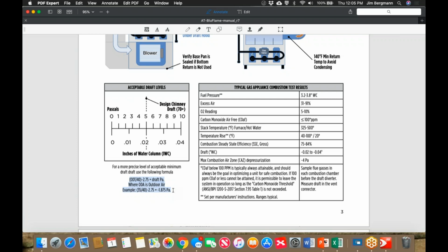It doesn't affect the appliance unless it's connected physically, like an oil burner is connected to the draft. So the draft plays a huge role in the amount of secondary air that is introduced through the combustion chamber. When you have a draft hood and it's connected to the appliance, it separates the appliance from the draft. So now the natural rising of the flue gases is what controls the gases through a draft hood equipped appliance. Where an appliance connected to the draft becomes very, very critical.